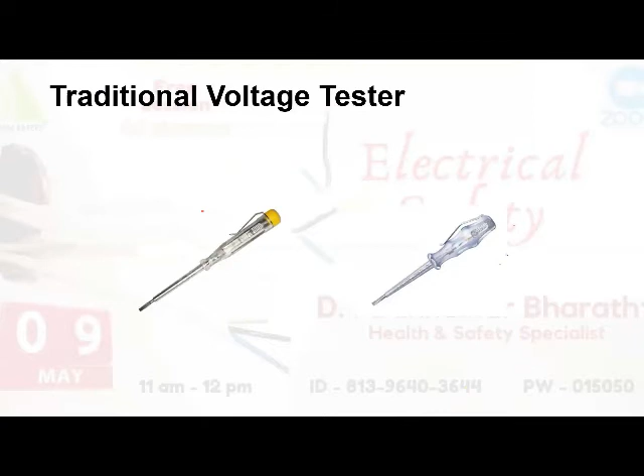And the traditional voltage tester, will it be allowed? It is faulty equipment. Again, it is unsafe equipment because there is no proper test and no proper rating. There is no standard for this conventional traditional voltage tester.